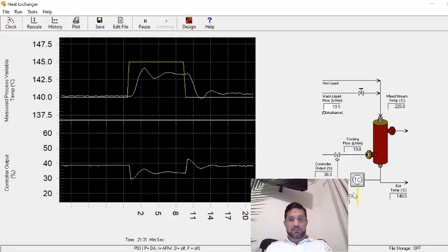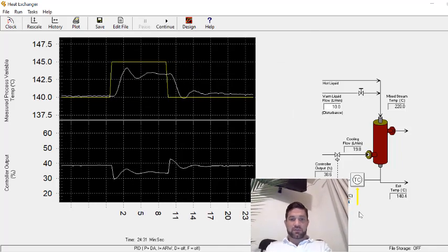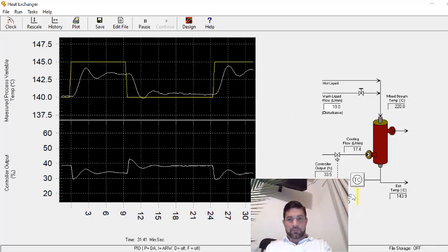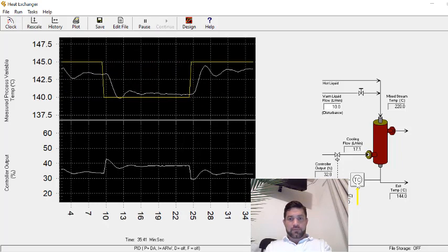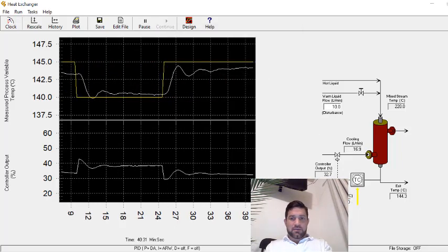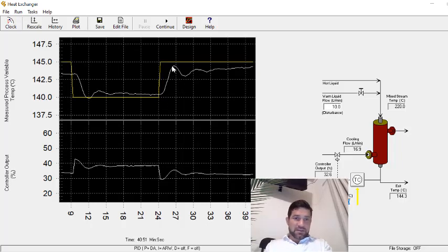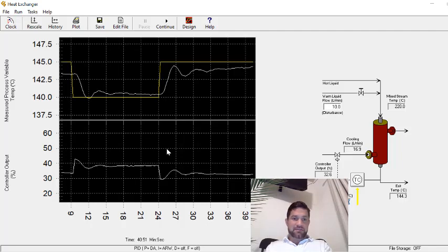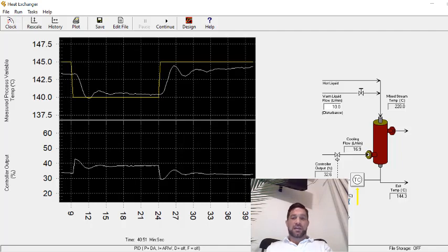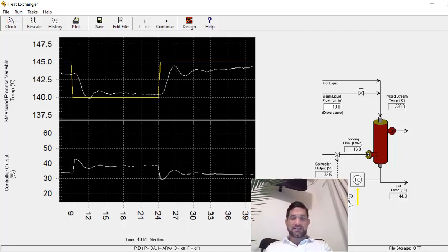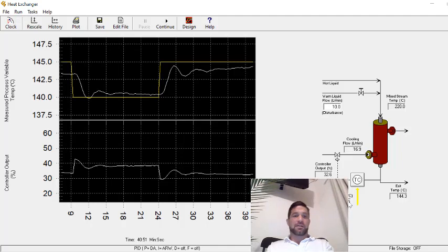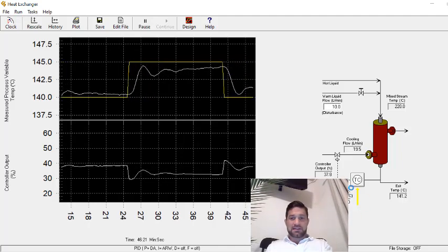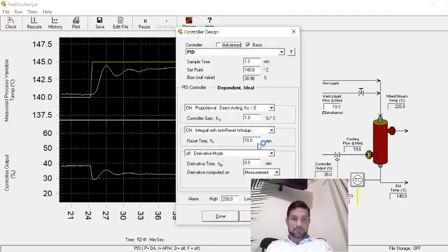Now we do our step change to 145. And now it looks like we're getting pretty close to this first peak to valley. We can see that peak to valley is about 16% of the step change. The time that it takes, we go from 24 to about 27, maybe that looks like 2.8. So on my controller, my reset time should be about 2.8, and I'm at about the right gain.